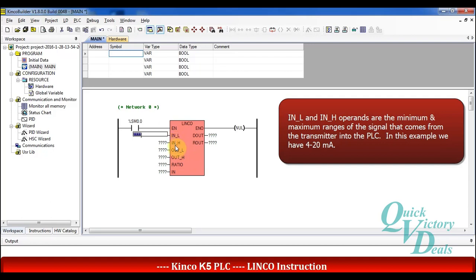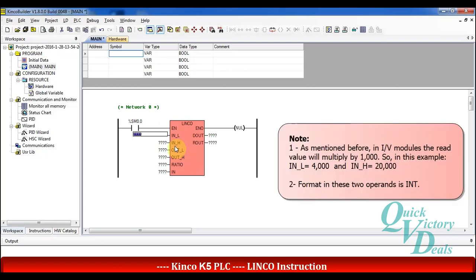The point we mentioned before is that for current or voltage input the value will be multiplied by 1000 in the PLC. So we should use 4000 for INL and 20000 for INH, and the format is integer.